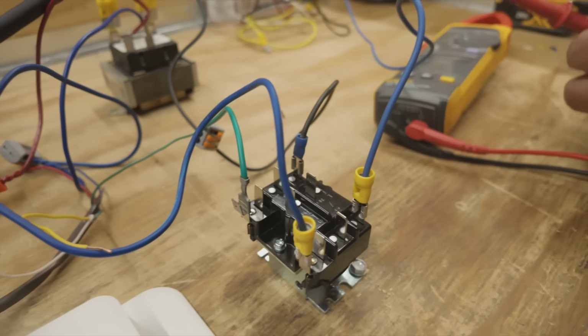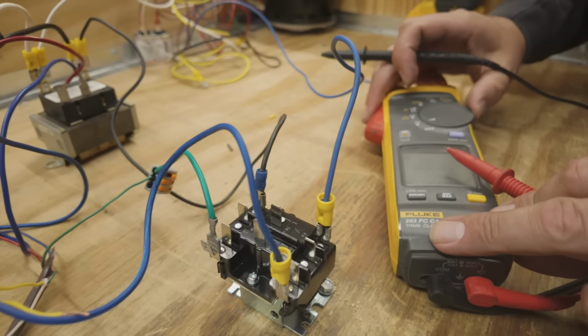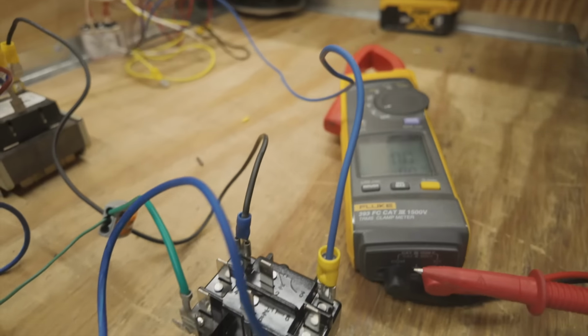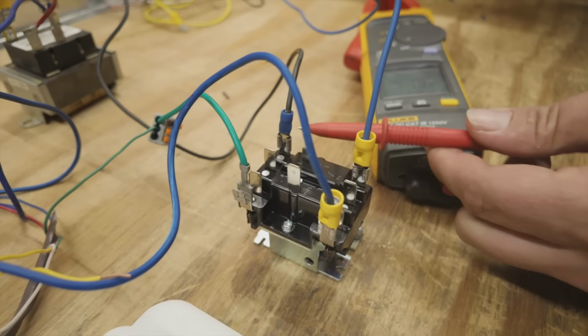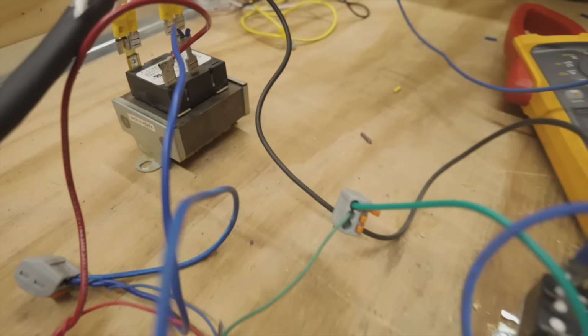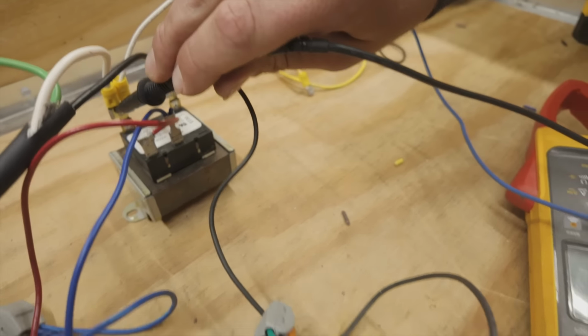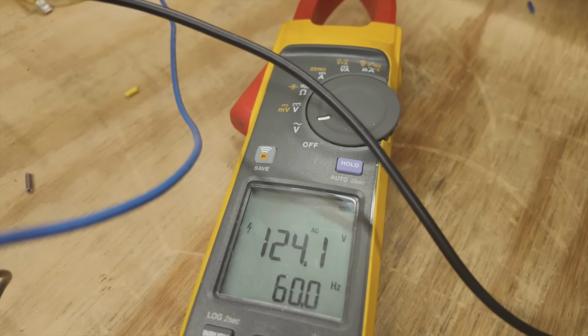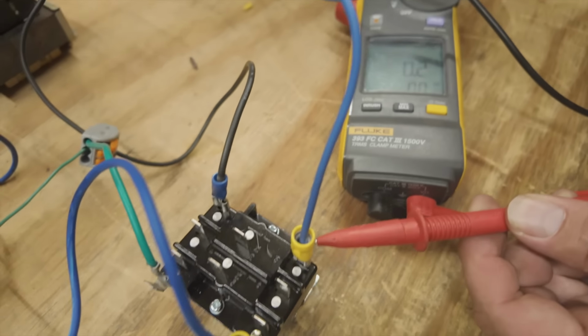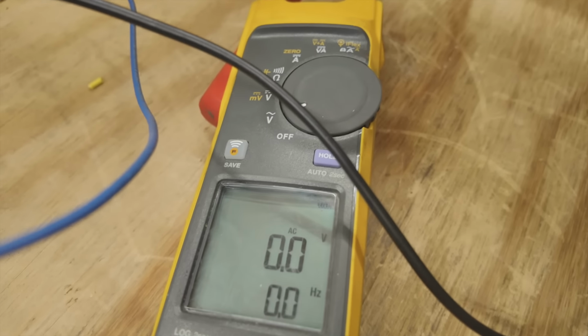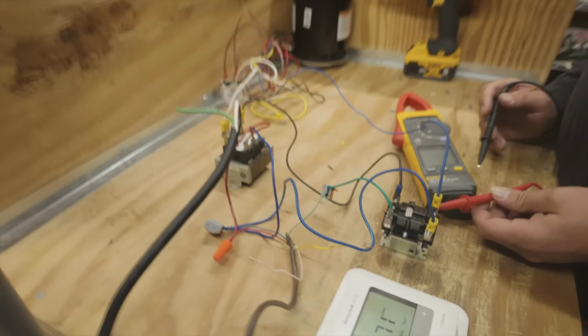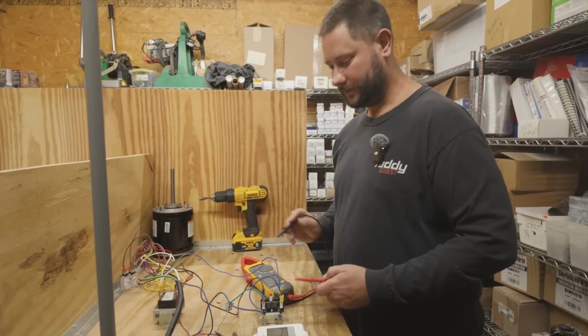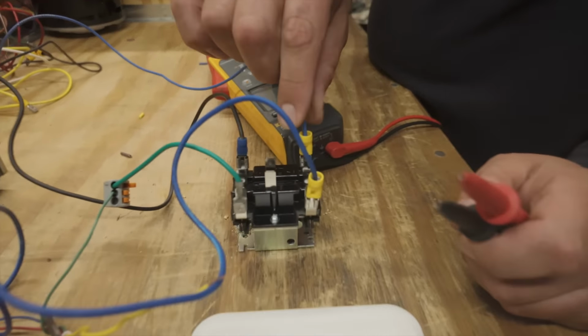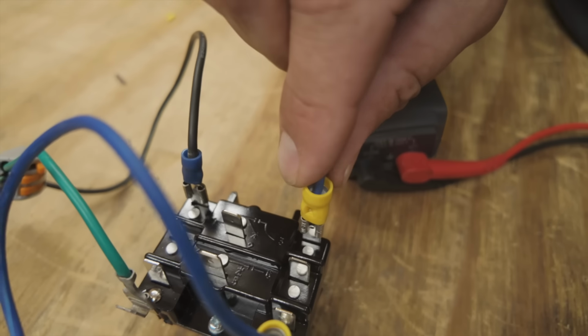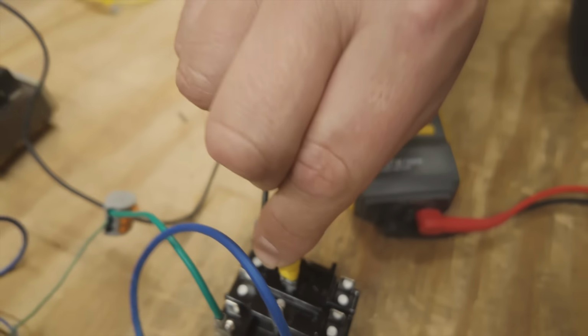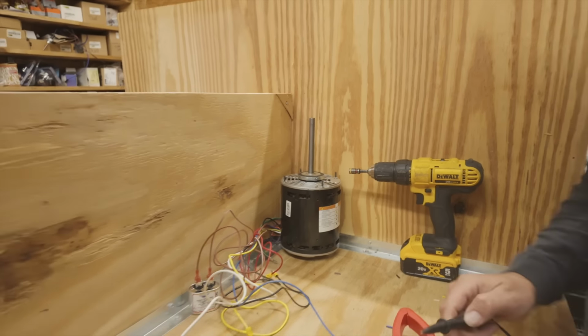All right, I'm going to use this speed for the other side. Now, here's another way to check. We're going to go to volts AC. All right, and I'm going to go to, let's see, this side and then this side. Together, we got 120, right? Look at that. 120. But this is a normally open relay, so if we go to the other side, what do we got? 0. All right? Because the power hasn't gone through yet. Now, if I take this same wire and I don't use 1 to 3, but I use 1 to 2, watch what happens. Motor kicks on.